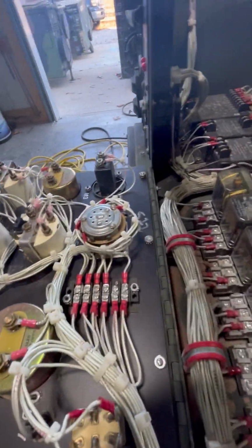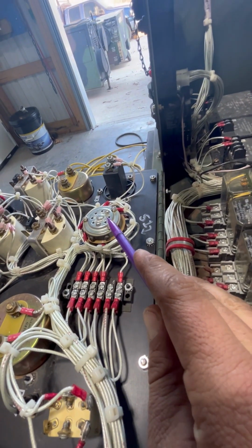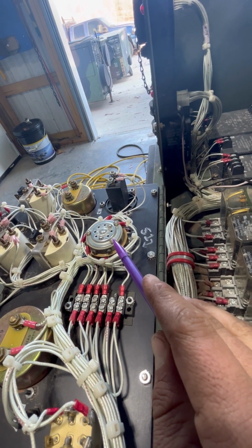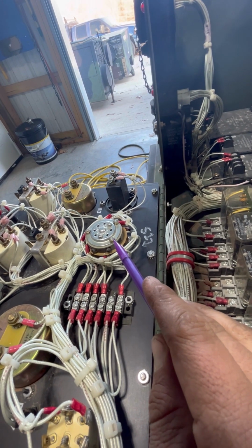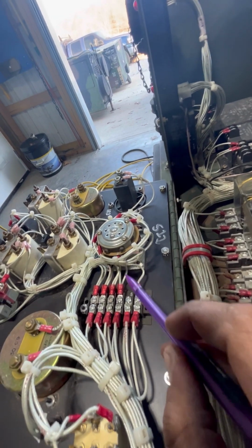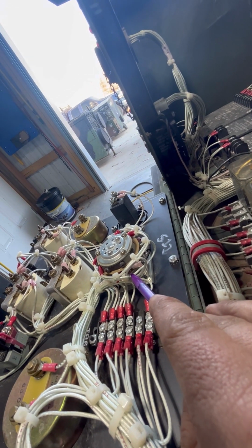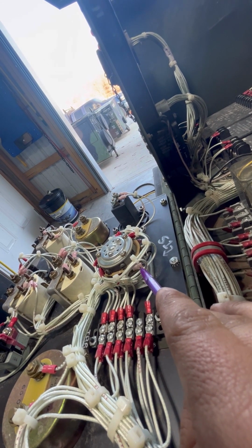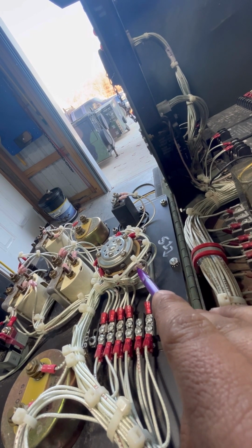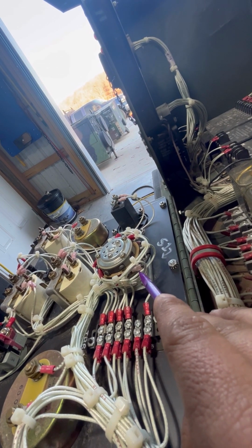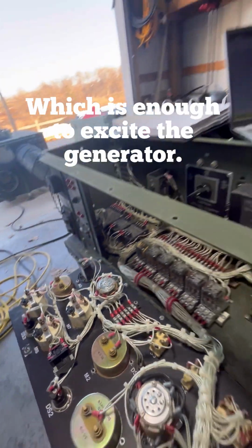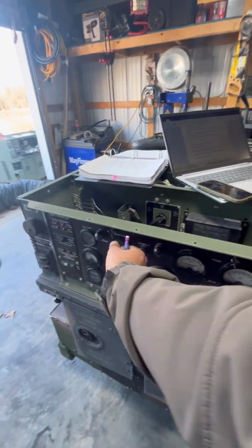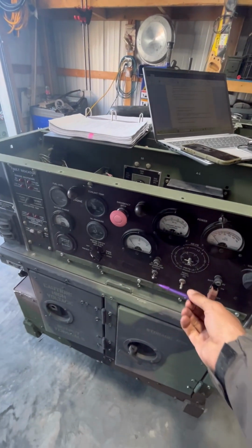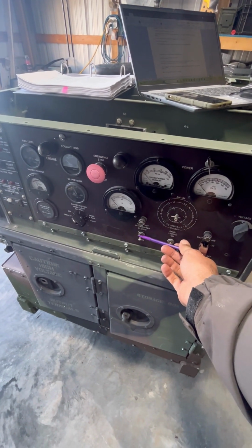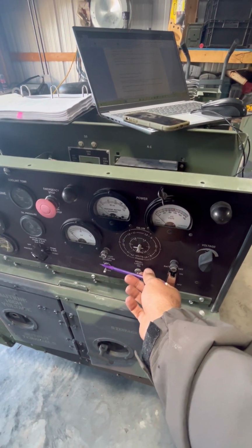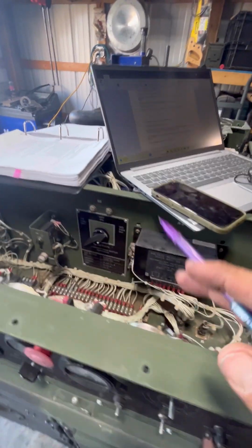So in order to test that, this is switch 1 right here. I went to switch 1. I started the generator normally, but I kept switch 1 in the start position. And I measured the voltage coming off of pin 7 right here, down here with this pink line. And I received 22 to 23 volts. And I verified that the switch was, in fact, working. Then from there, I went to the technical manual, and I verified that the interrupter circuit switch was operating correctly, and it was.